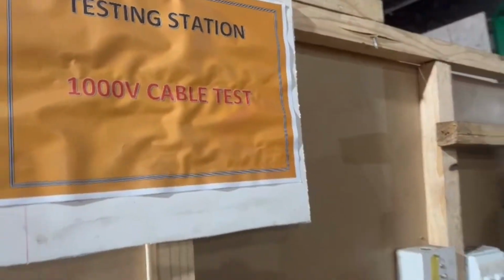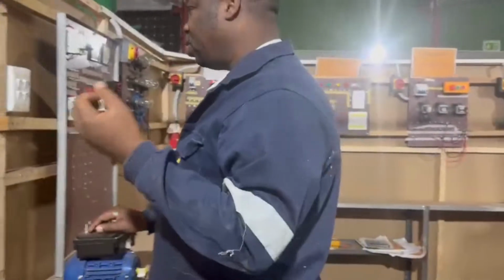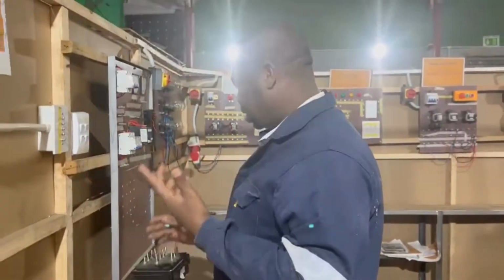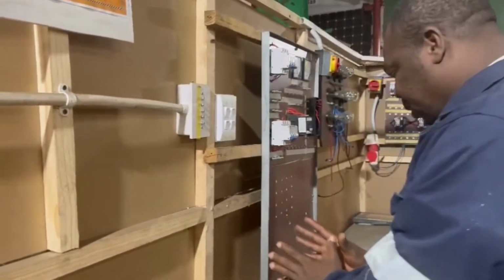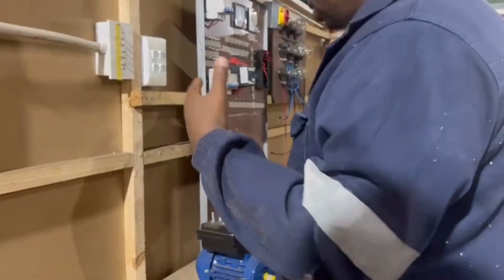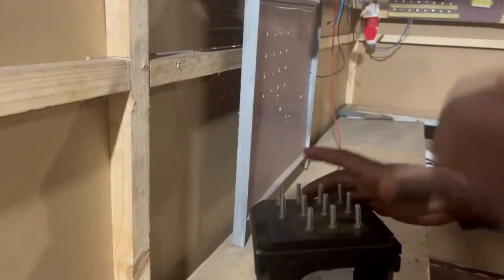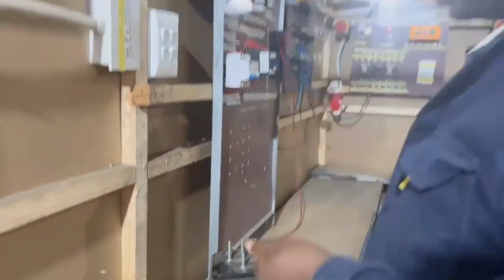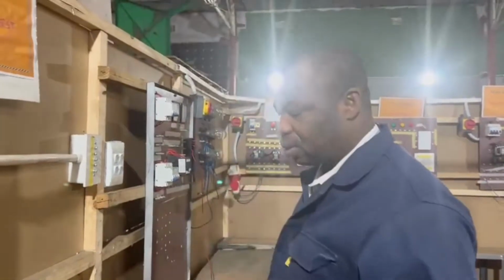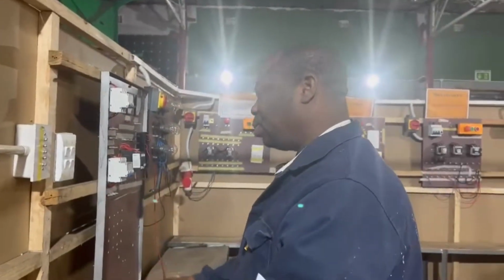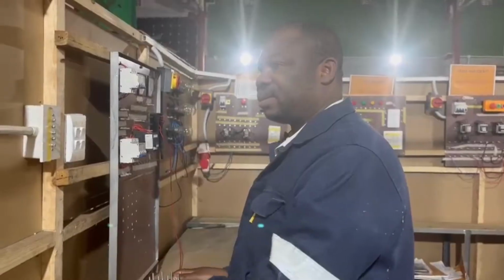So out of these 4, the assessor is going to assess you on 1 of them. For the 3 motors, you have to do the mechanical test, and you are also going to carry out the electrical test. After the test, you need to conclude whether the motor is in good condition to be used in electrical systems.